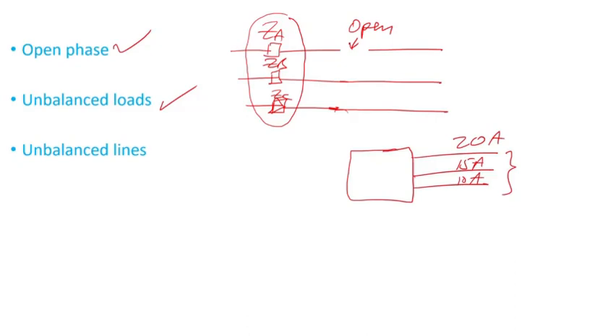And that's why you have to, with the feeders or transmission lines, you have to roll, you have to rotate the phases, and also you have to transpose them every so many feet or miles, so you can create kind of an equal impedance, also the same conductor. Because if the impedances are not the same, then you will have unbalanced situations.